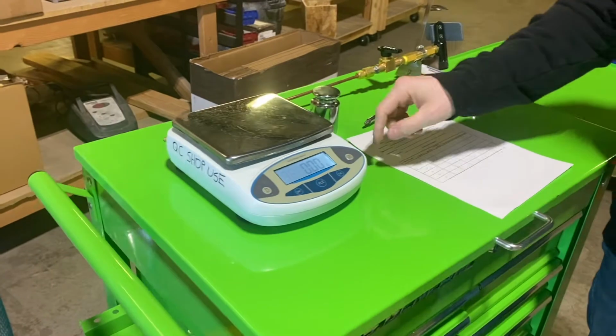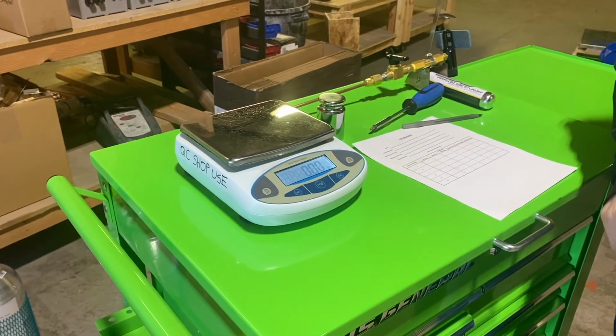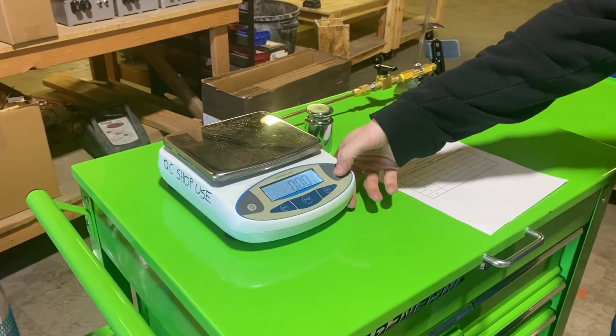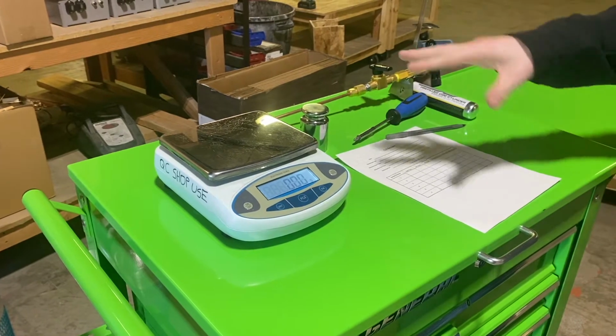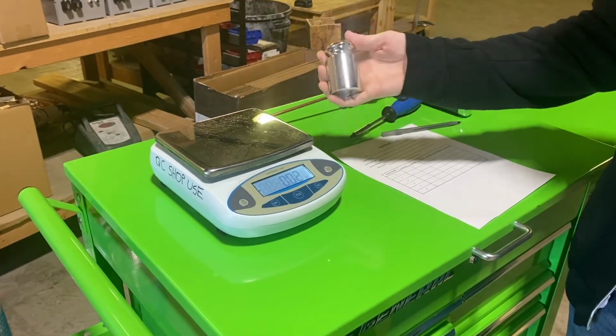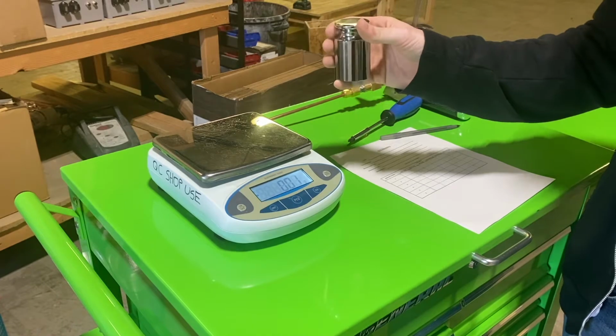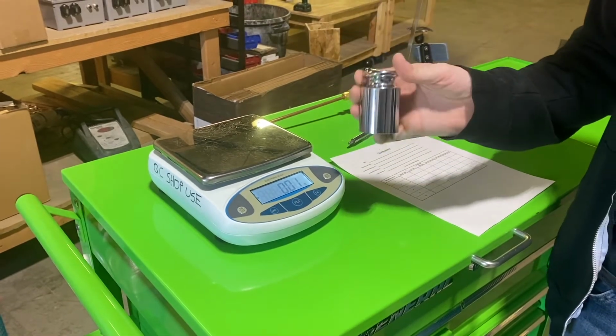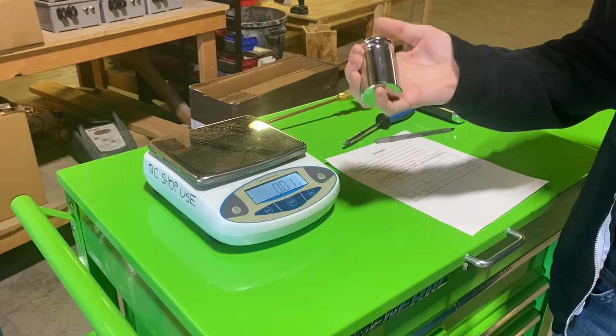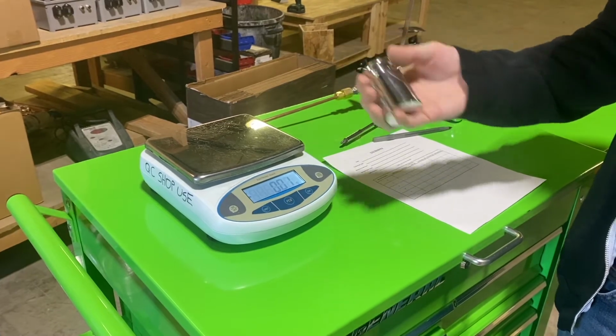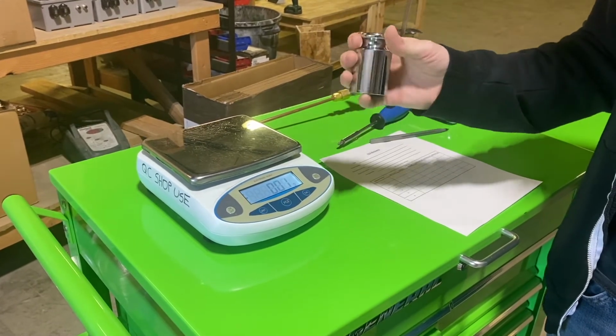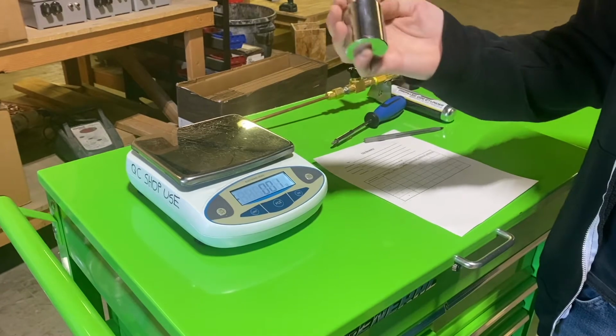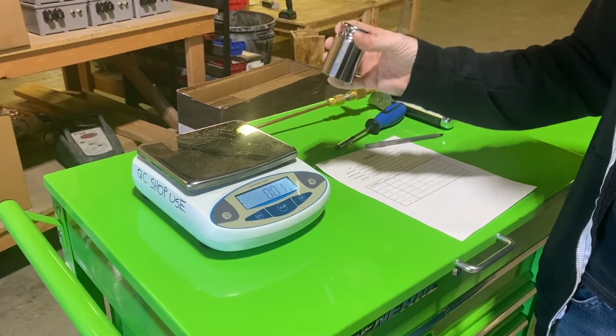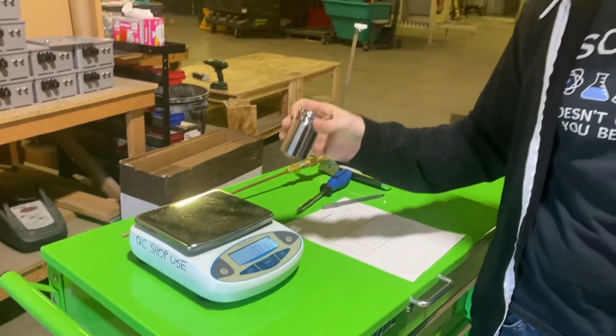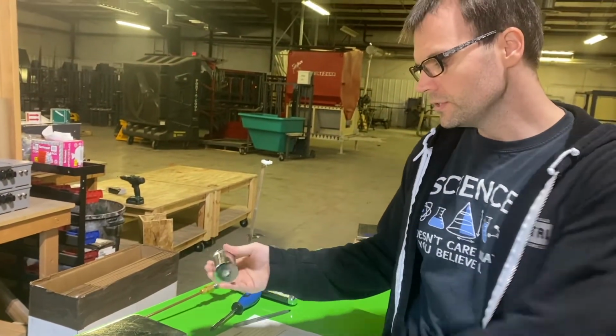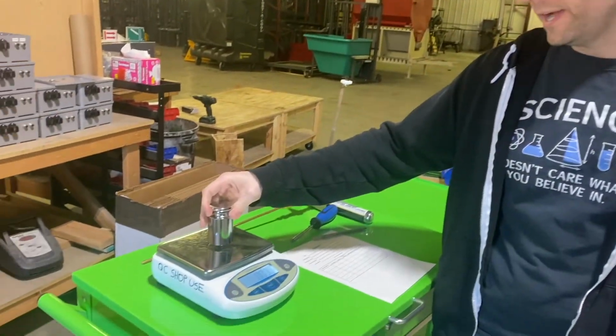Once you have it set up, if your scale does not read 0.00 grams, press the tare button, and that will make sure that it reads 0. And now we're going to use our 1 kilogram calibration mass. If you don't have this 1 kilogram calibration mass, then you can use any small 1 to 2 kilogram weight, but we want to make sure that it's reading reliably. So make sure that every time you weigh this, it gives you the exact same number every time.